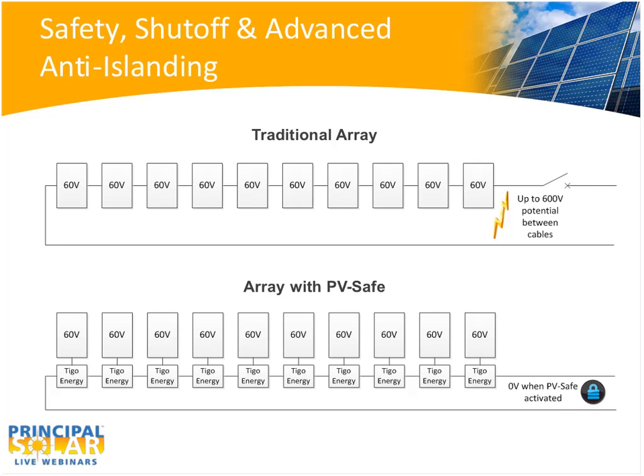And then there's no voltage in series, so those cables home are going to be at 0 volts the whole time. That's a very nice benefit today because you can make sure that your maintenance workers and any emergency workers are always going to have a safe environment. But this type of shutoff, making sure the system is below 70 volts, that's actually how the code is written.